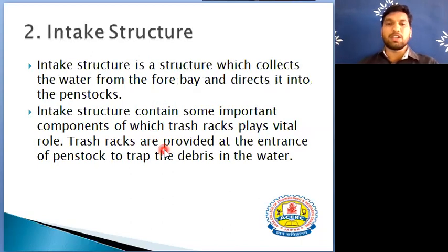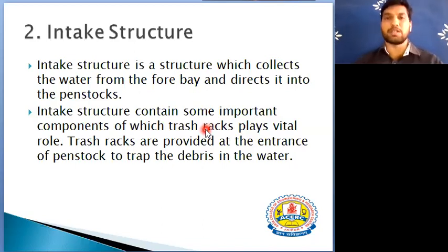Now the next part is the intake structure. Intake structure is a structure whose function is basically to regulate or control the flow of water. The flow of water is regulated with the help of control valves, or we can say regulatory work is done with the help of the intake structure. In the intake structure, the trash rack also plays an important role because it prevents the entry of debris into the penstock, or the entry of debris or silt which could strike the turbine. So the trash rack is also an important part of an intake structure which is used to prevent the entry of debris into the penstock.